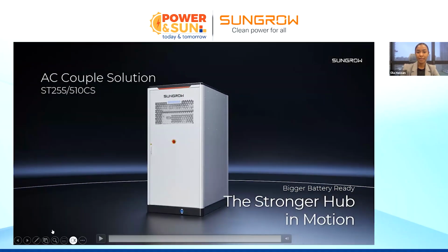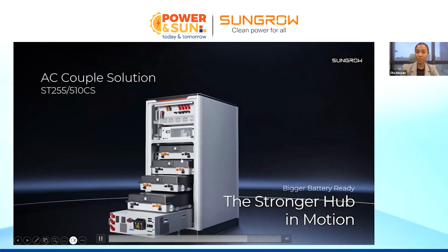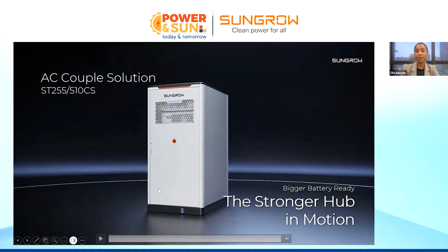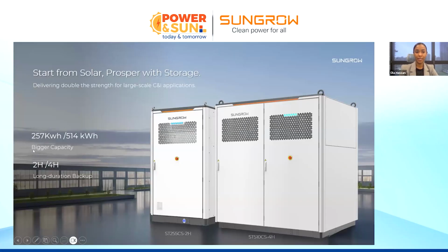As we can see here, this is how the AC coupled system looks. It's a modular cabinet. It's IP65 rated. It's also liquid cooled. The PCS is on the top, the battery racks are on the bottom, and the AC distribution box is on the bottom side. This cabinet comes with 257 kilowatt hour, that's the usable energy. And we also have the 514 kilowatt hour usable energy, which is the 510 CS. So one cabinet is 255 and two cabinets will give us 510. PCS capacity is 125, as we can see over here. So it is suitable for 2-hour systems and 4-hour systems. Both of those models fit the application scenarios that I've explained earlier. So we can select our energy storage capacity and PCS according to our application.